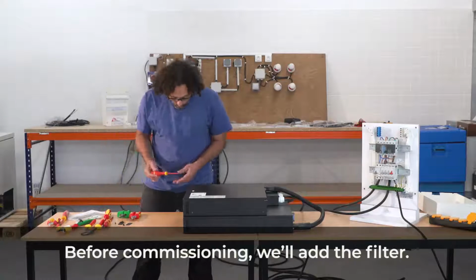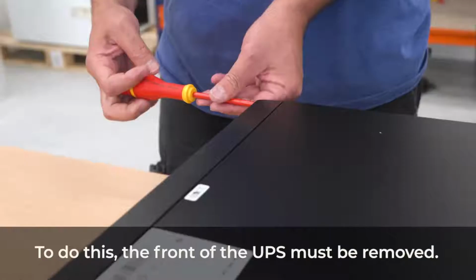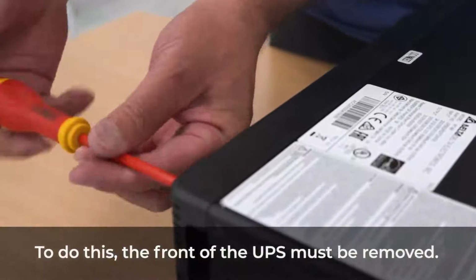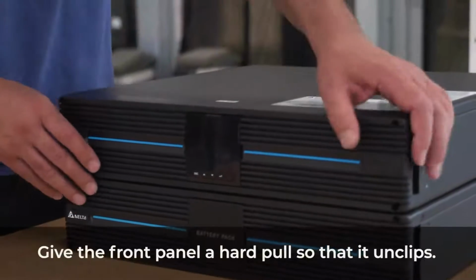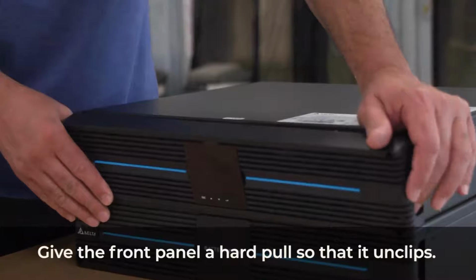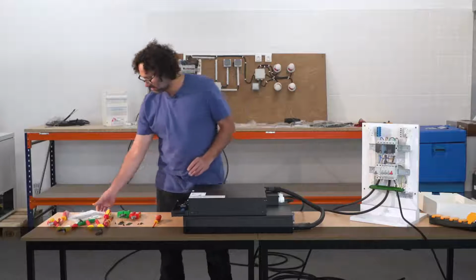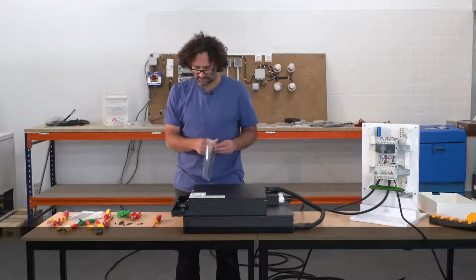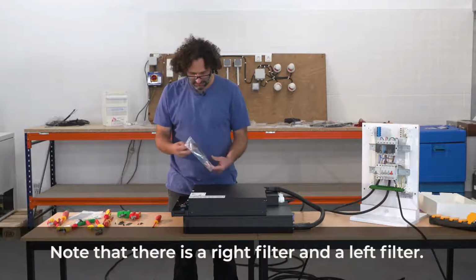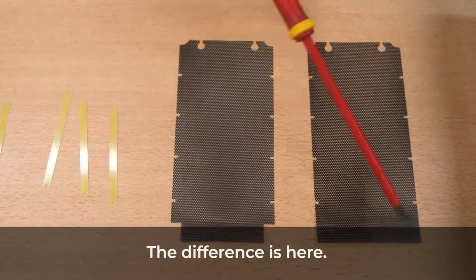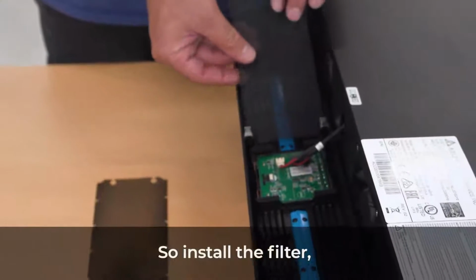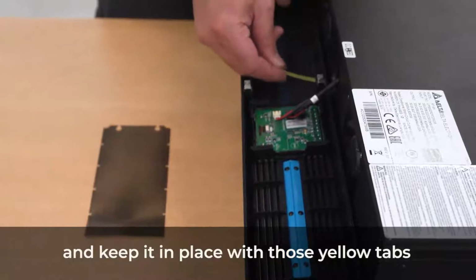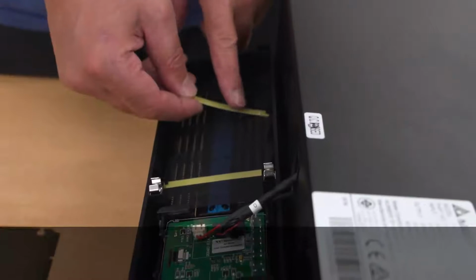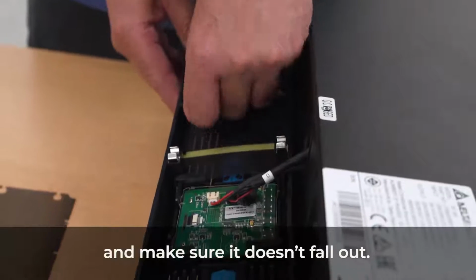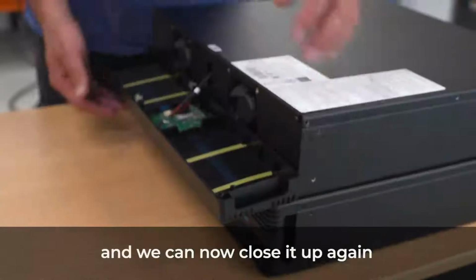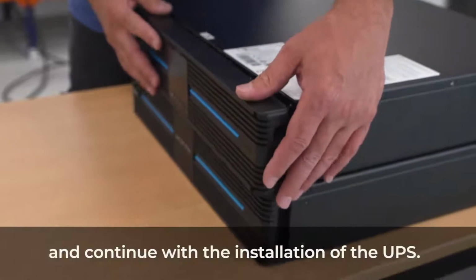Before commissioning, we'll add the filter. To do this, the front of the UPS must be removed. Give the front panel a hard pull so that it unclips. In this part, we'll add the filters. Note that there is a right filter and a left filter. The difference is here. So, install the filter and keep it in place with those yellow tabs that are used to secure it, and make sure it doesn't fall out. We put in the two filters and we can now close it up again and continue with the installation of the UPS.